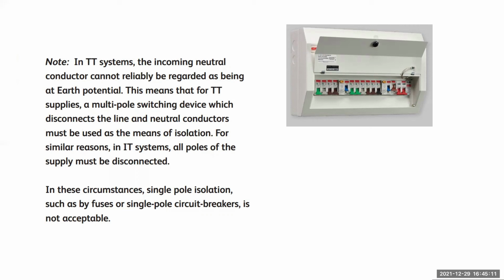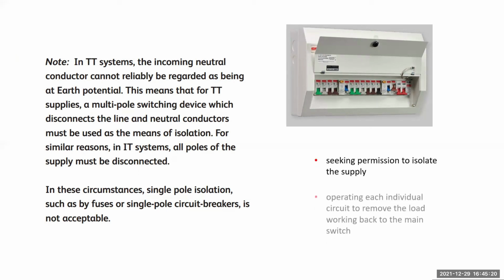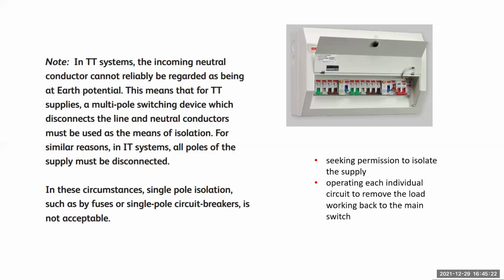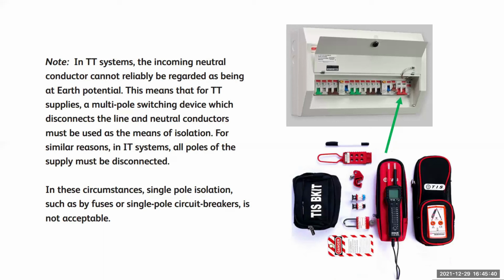So next time you're standing in front of a consumer unit or accessory looking to gain entry to the live part, don't forget to seek permission to isolate the supply, remembering that the main switch could be an isolator and not a switch, meaning that it may not be designed to be turned off under load. In this case, operating each individual circuit to remove the load and working our way to the main switch, we can avoid damaging the main switch. Then secure the main switch in the off position with a suitable lockout kit.